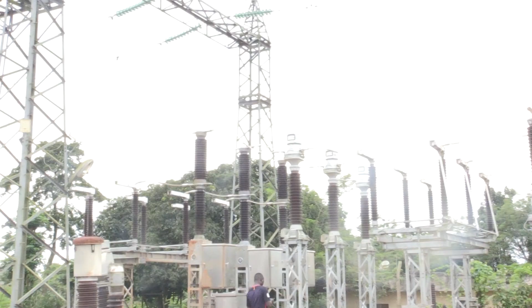We have a 60 MVA and a 30 MVA in service, with 5 feeders total—3 feeders on the 30 MVA and 2 feeders on the 60 MVA. The station was built around 78-79, so it has been around, and it has been upgraded gradually from 30 to 60, with an additional 60 added. Presently there is 100 MVA that has been installed, on soak.